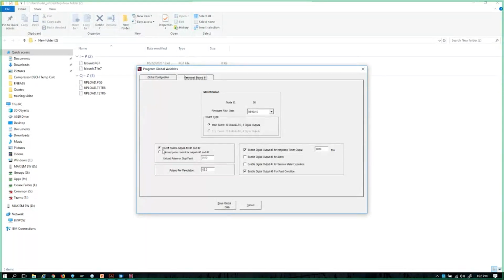It gives us a few options. On-off control for outputs 1 and 2. Again, by default, that's the most common. Or solenoid pulse control for outputs 1 and 2. And here's where I can change that. So if I was setting up something for a screw compressor application, or any application where I needed to pulse something on and off, I might use this selection right here. And then it's asking, if I do use solenoid pulse control, what do I want to do at unload: pulse, stop, fault? I can tell it basically how fast to start unloading the system.